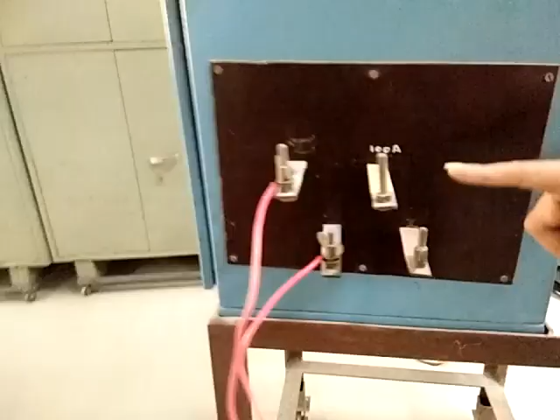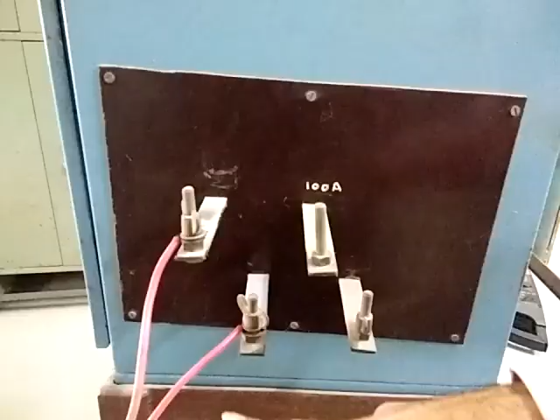Now we will see the variation in current. I will inject the current. For that purpose, I have connected a sample cable between common and 50 ampere terminals. Through this sample cable, I will inject some current.